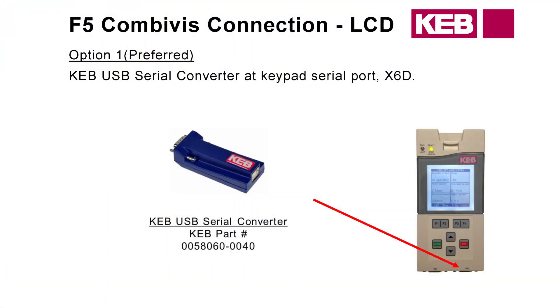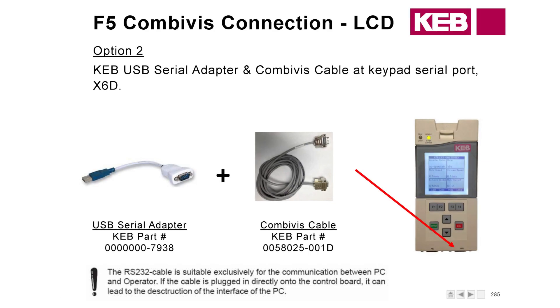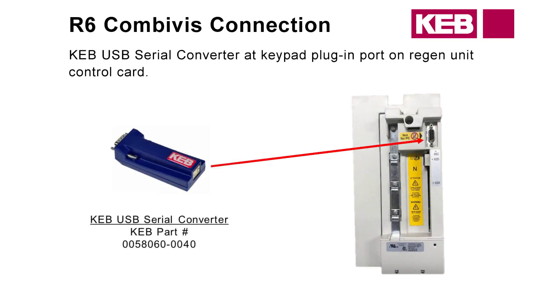If you wish to connect to the new style keypad, all you need is the serial converter — that's it. You're going to make the connection right here on X6D. If you're using serial speed control with the controller, that's going to be connected on X6C, so we have that extra diagnostic port available. If you're looking to connect directly to the control card on the R6, that's going to be right here.